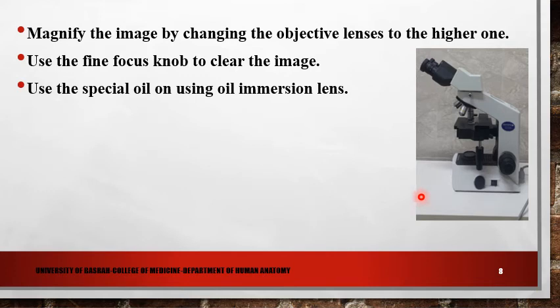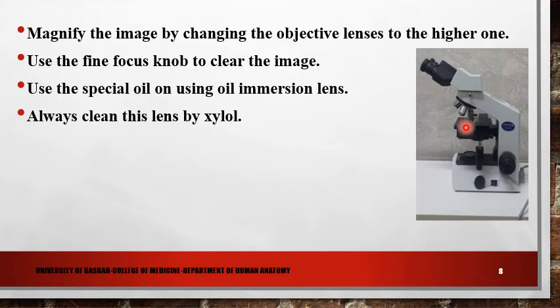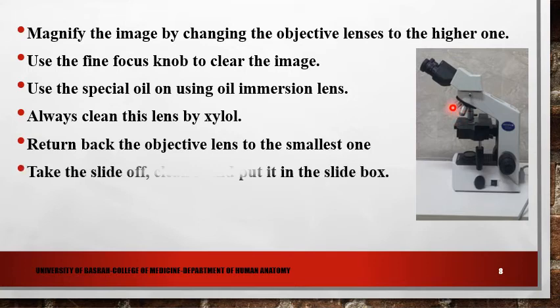Use special oil when using oil immersion lens at 100x. Always clean this lens with xylol to remove the oil from both the lens and the slide. Return back the objective lens to the smallest one, 4x. Take the slide off, clean it and put it in the slide box.